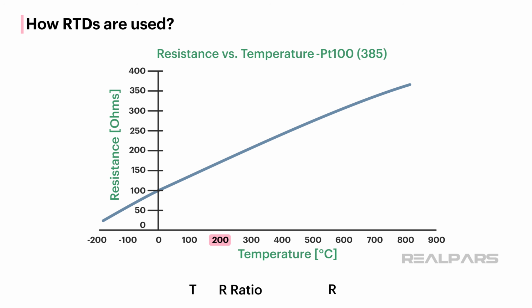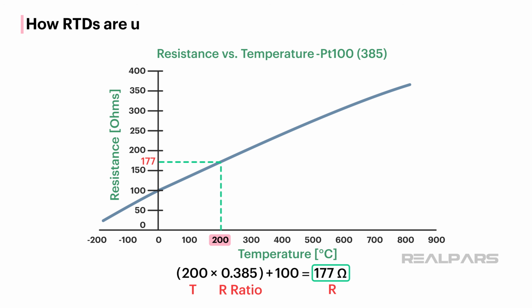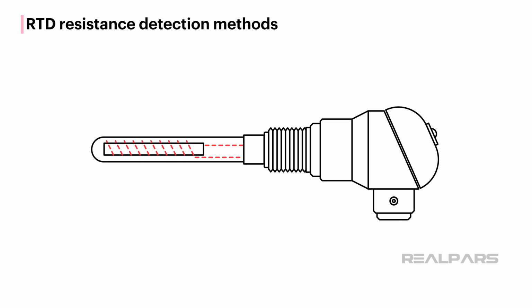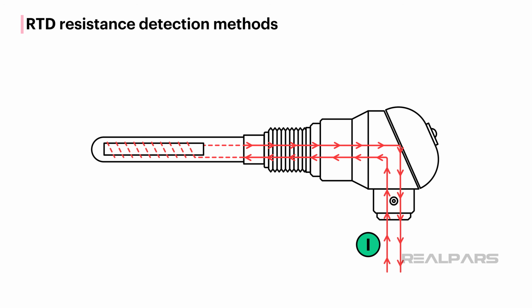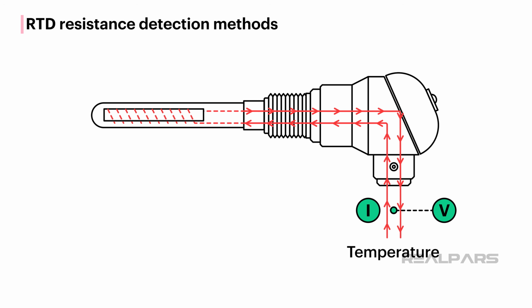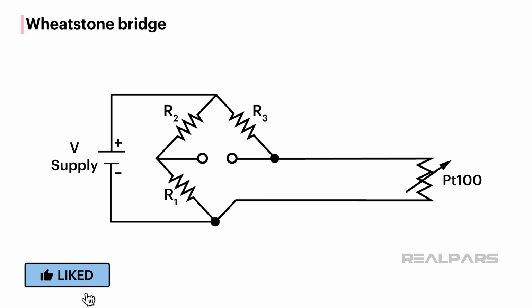Assuming a temperature of 200 degrees Celsius, the resistance of the PT100 RTD is 200 degrees Celsius times 0.385 ohms per degree Celsius plus 100 ohms equals 177 ohms. That's what we see from the graph as well. Okay, let's look at how we detect RTD resistance in industrial applications. Earlier, we stated that a current is passed through an RTD, and we detect the resulting voltage across it to determine temperature. The Wheatstone bridge was probably the most commonly used method originally, but it's not so common anymore. We will discuss other methods, but first, let's look at the Wheatstone bridge.